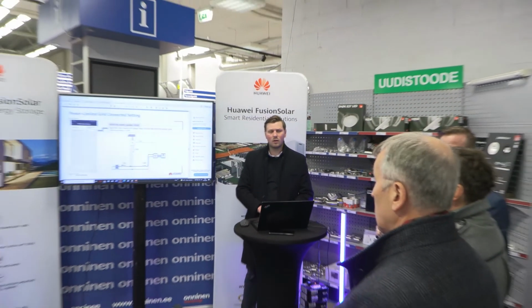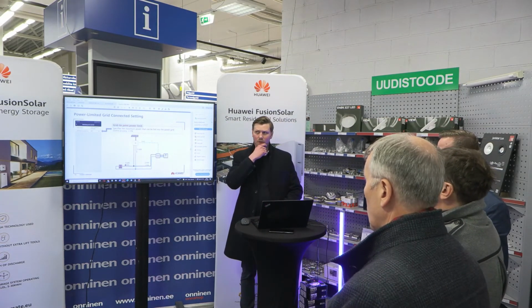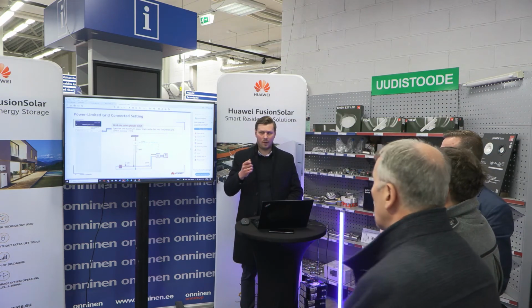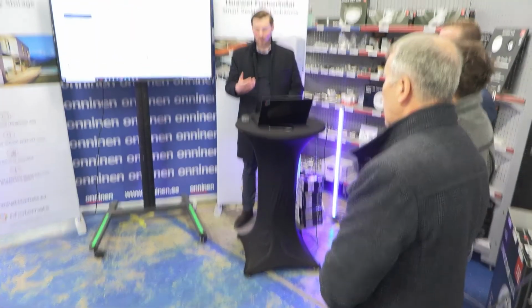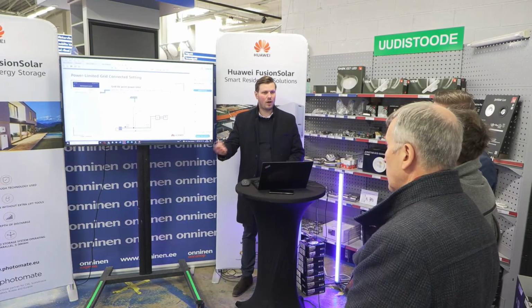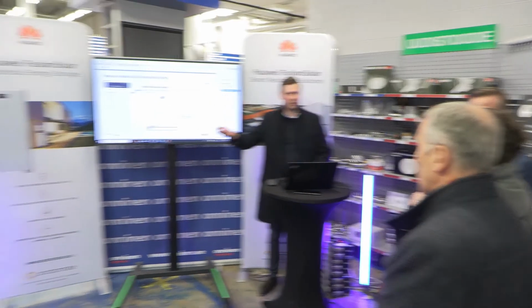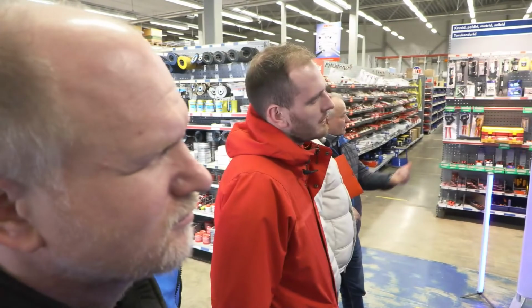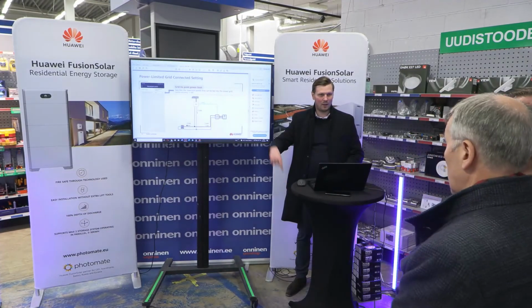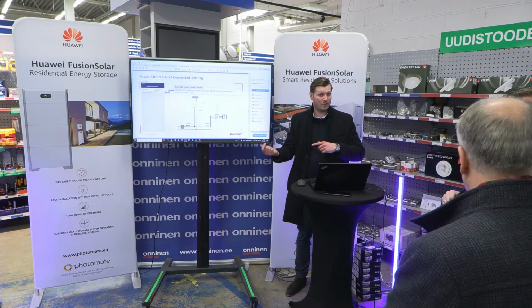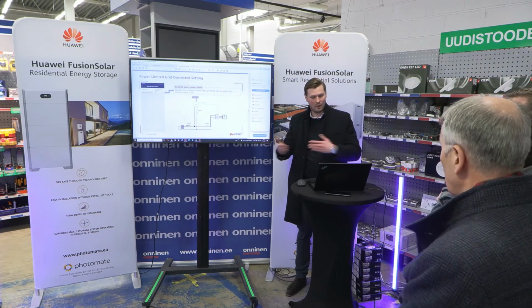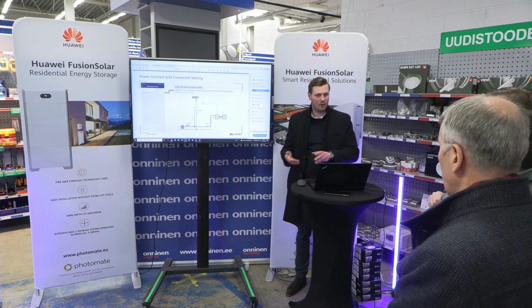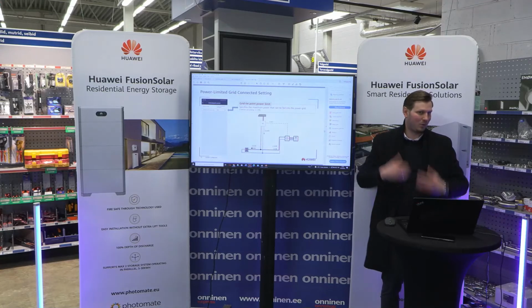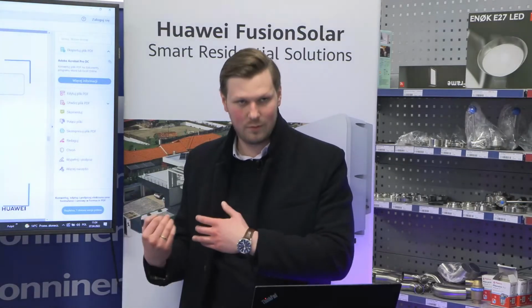It's also a very nice solution if you have an Ethernet network in the building — you can use an Ethernet to RS485 converter to convert the signal, for example across 5 floors from the rooftop to the basement, using the Ethernet connection, with another Ethernet to RS485 converter on the other side converting the signal back to the inverter.